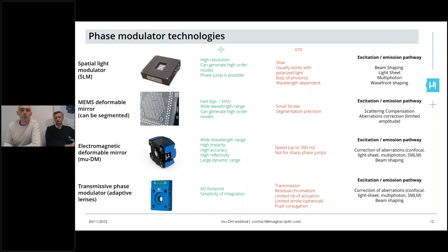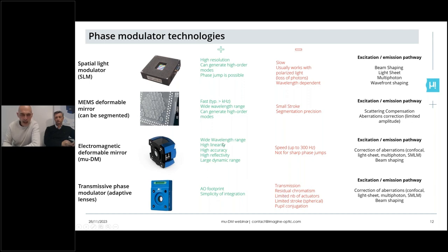There are also currently limitations in the number of actuators and stroke achievable with transmissive devices. Even if placed just after a microscope objective, pupil conjugation will not be perfect because they cannot be integrated at the exact pupil plane. The last family is electromagnetic deformable mirrors, which we will now discuss in detail.